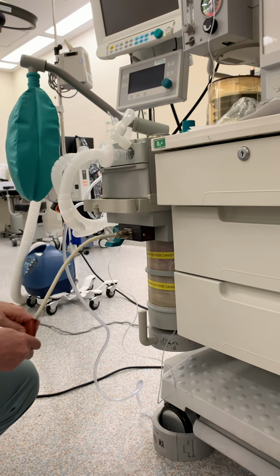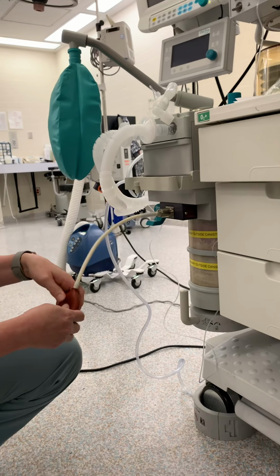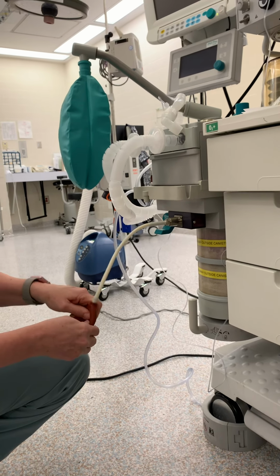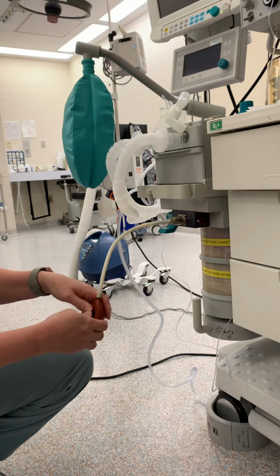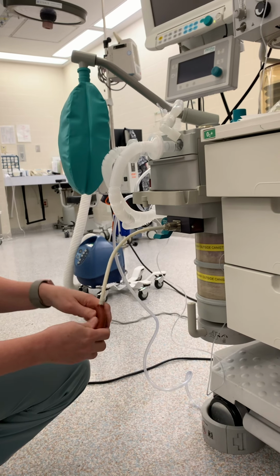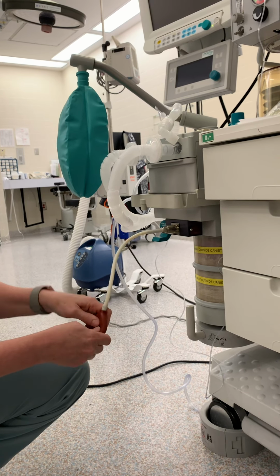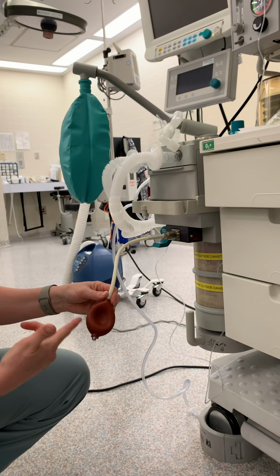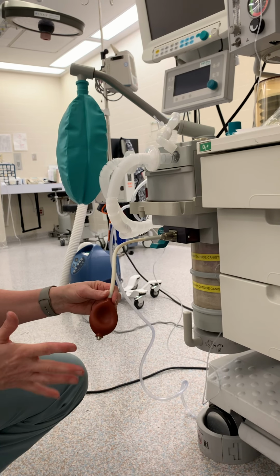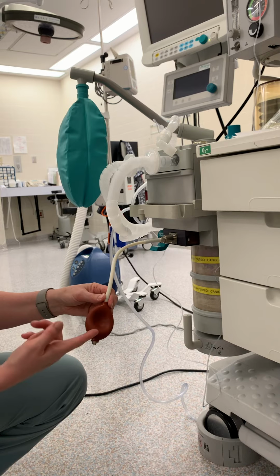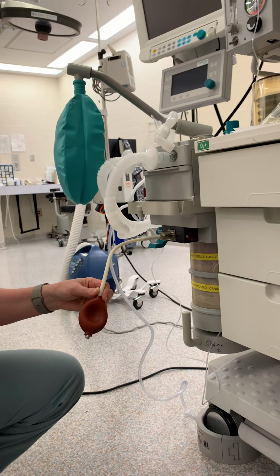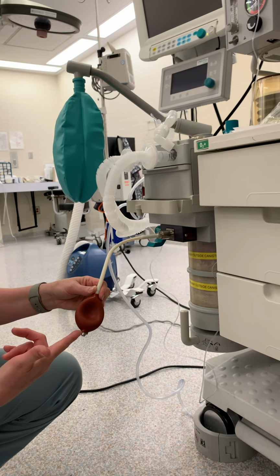You want to deflate the balloon. You're just getting rid of all of the excess gas, and you're trying to set up a negative pressure environment. Once you deflate the bulb, you want to make sure that it stays deflated for hopefully up to 10 seconds, and this bulb has remained deflated so that it passes this test.